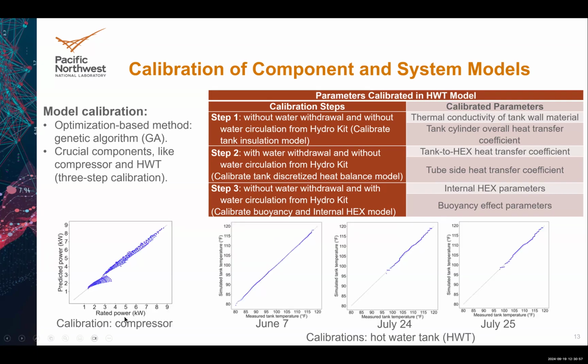The left figure shows the calibration for the compressor. By the way, for compressor calibration, because we have the manufacturer data, this is actually enough. So we use the manufacturer data to do the calibration. If you look at the x-axis, we have rated power. The y-axis is the predicted power.